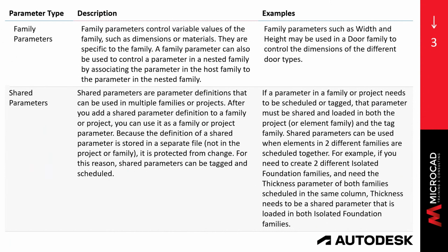So if a parameter in a family needs to be used in a tag, or you want to make sure that you can schedule them, and that is going to be part of my demo, it needs to be created as a shared parameter and loaded both in the project and in the family.